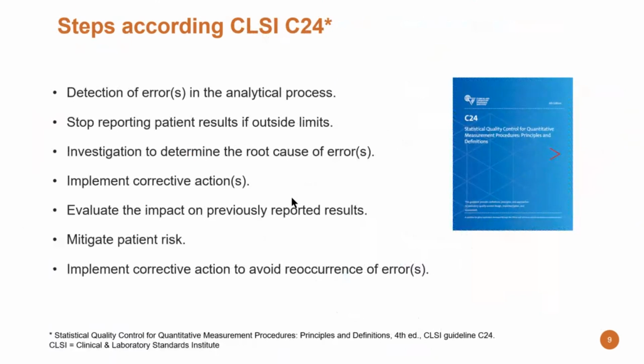There is a document provided by the Clinical and Laboratory Standards Institute called C24. Within this document, there are different steps for proper troubleshooting: detecting the errors in the analytical process, stop reporting patient results if they are outside the limits of the QC, investigation to determine the root cause of the error or errors, implement corrective actions, evaluate the impact on previously reported results, and finally mitigate patient risk, and implement corrective action to avoid recurrence of errors.